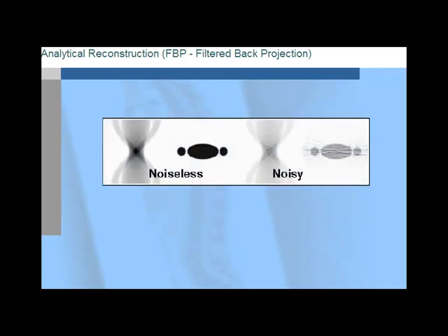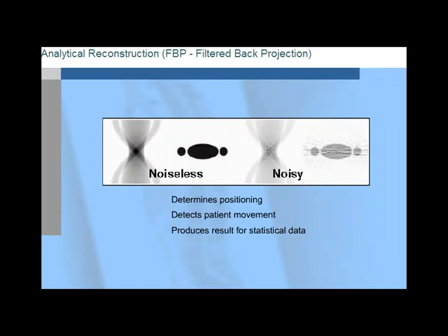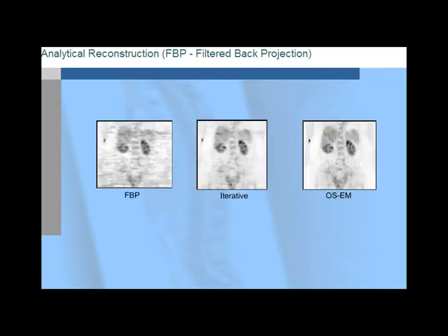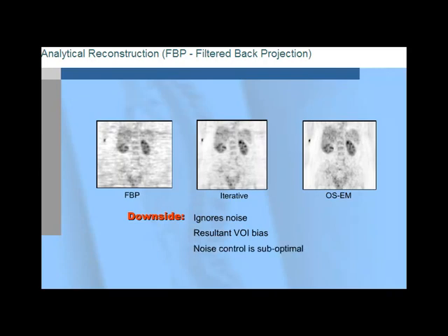FBP is employed for general PET, so it is used for reference images. FBP is effective — it can help you determine positioning and detect patient movement. It produces the correct result for high statistical data and will also generate an image to tell you where you are. Of course, FBP has its downsides and limitations. Primarily, FBP ignores noise, which gives all projections equal weight. So when highly attenuated lines of response are noisy and produce streak artifacts, the result is a bias in volume of interest, or VOIs, or correlated noise. Furthermore, FBP noise is controlled through linear filtering in sinogram space, which is suboptimal.